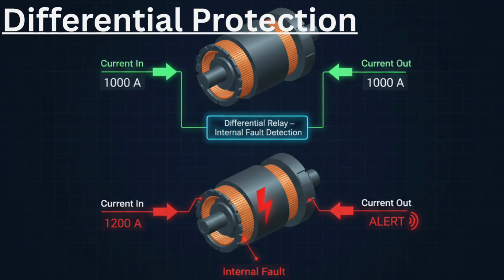Differential protection is mainly used for generator stator windings and transformers. It compares current entering and leaving the equipment. Under normal conditions, both currents are equal. If internal fault occurs, difference appears between incoming and outgoing current. Differential relay detects this difference and trips instantly. This protection is very sensitive and fast. It prevents major internal damage to expensive equipment. Differential protection is especially important in large power systems.